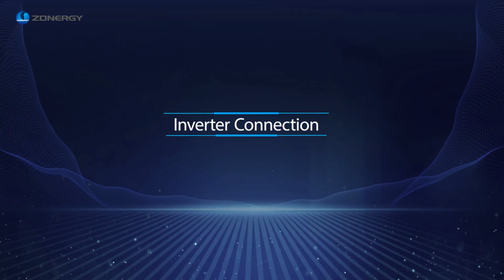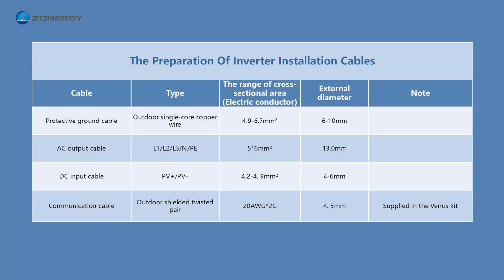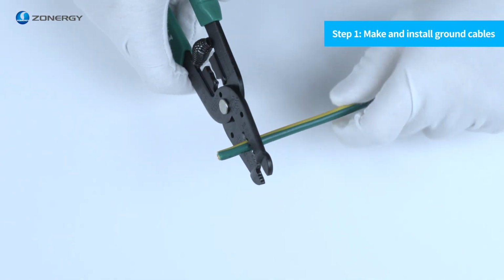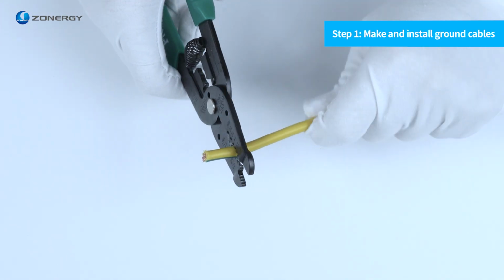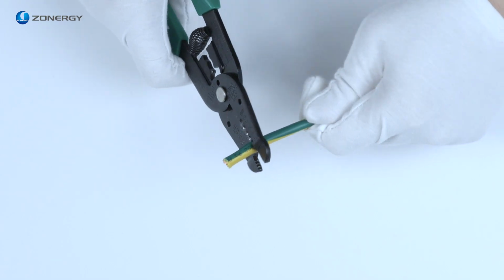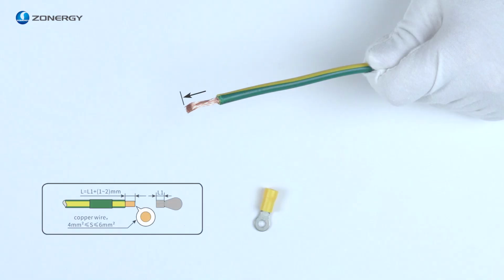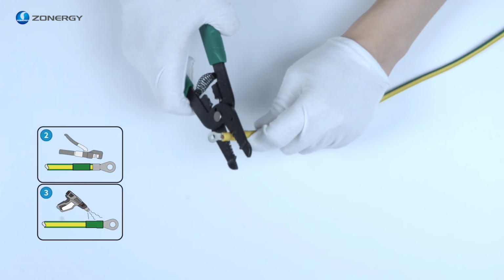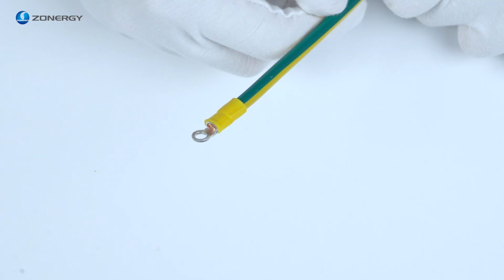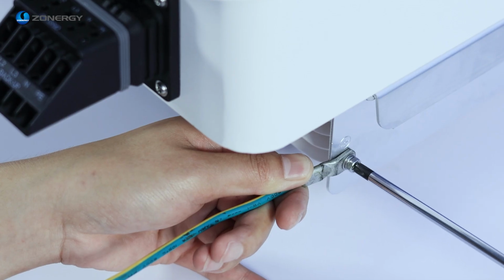Chapter 4 Inverter Connection. Preparation of battery installation cable. Step 1. Make and install ground cables. Wear insulation gloves to prepare a ground cable and connect it to the inverter. Make cable connectors of appropriate length according to the labels. The following is a prepared ground terminal. Connect the ground terminal with the inverter.